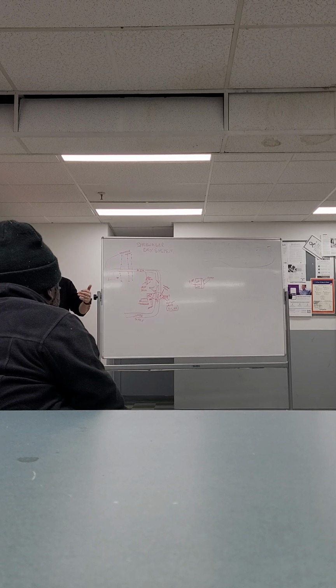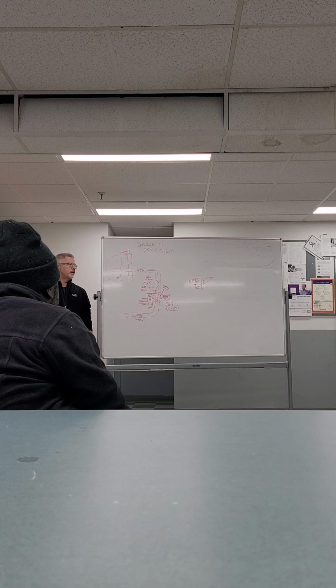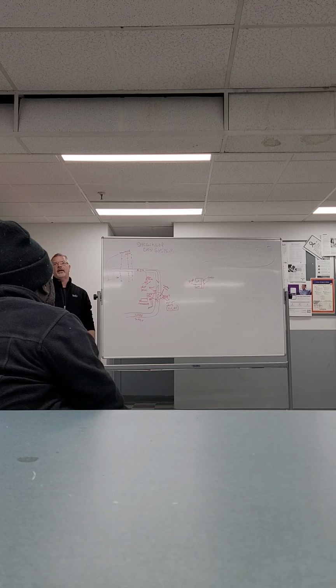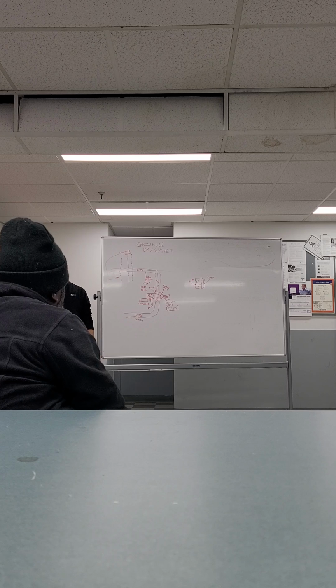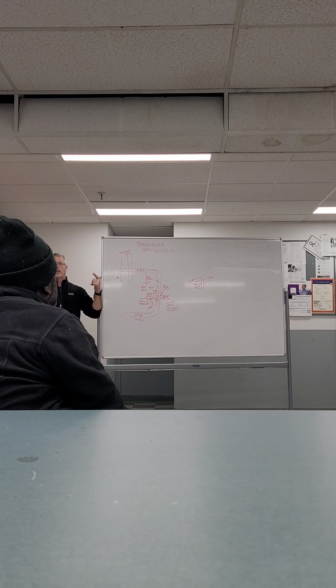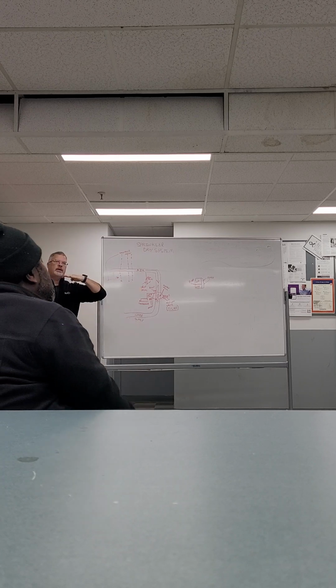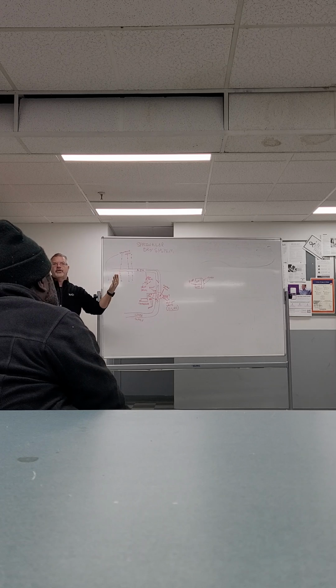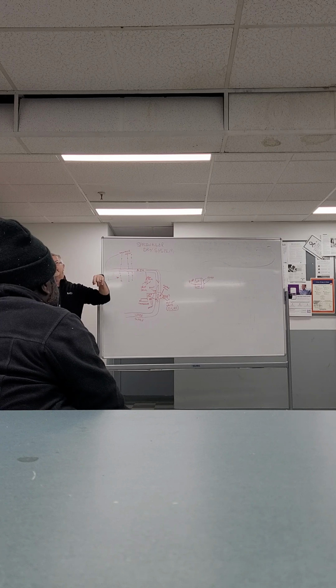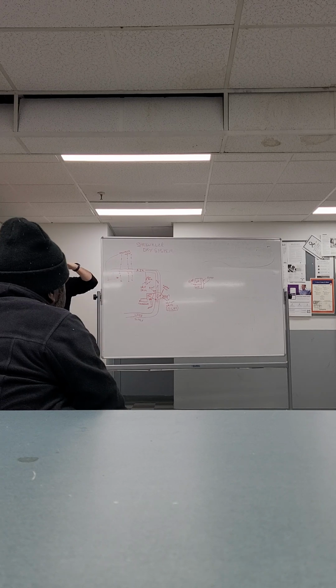The other thing that we'll get, like in the fire alarm, is if the compressor's not running normally, you'll get an alarm at the fire panel that says low air. That tells you that the compressor's not running, or the sprinkler line let go and the compressor can't keep up. Once it gets below, I think, 20 pounds of pressure, the alarm goes off. That way, we can be proactive. If we see a low air, we can run out there and isolate the valves before the flapper goes. Because once you get low pressure, that flapper valve is going to open up.